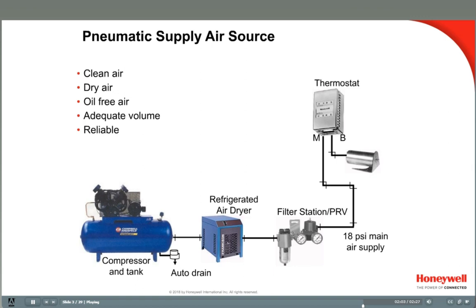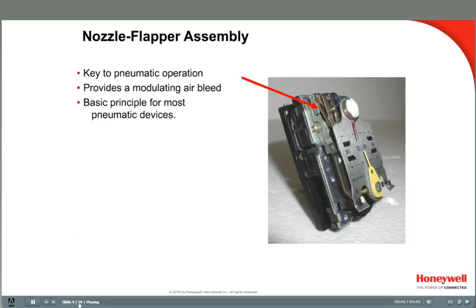The switchover may also occur manually between summer and winter. The pressure-reducing valve is usually in a mechanical room, but in larger buildings the air is delivered at high pressure to various parts of the building, with PRVs used to control pressure at remote locations such as distant wings or floors. In general, before considering the calibration of any controller, ensure that the supply of air is clean, dry, and at the correct pressure.